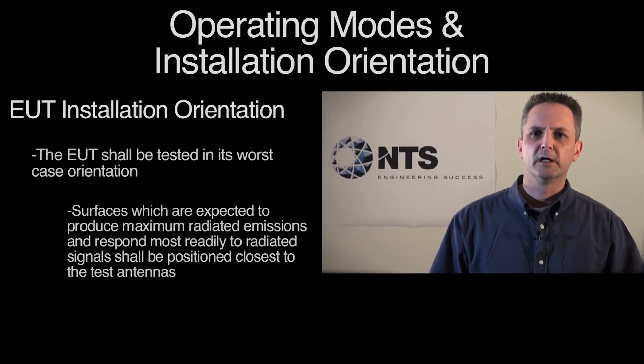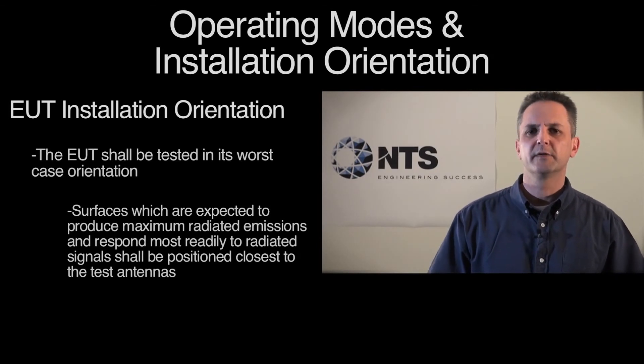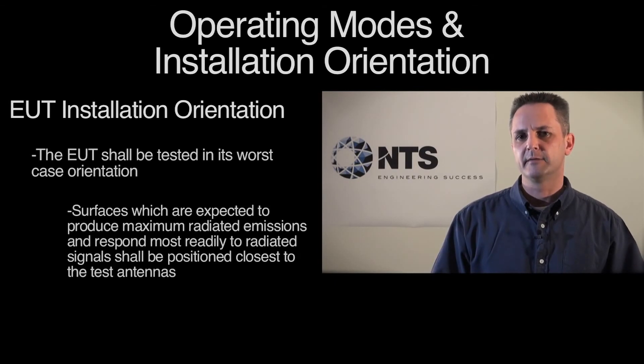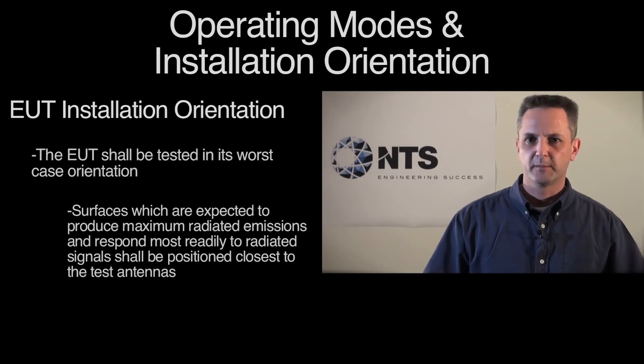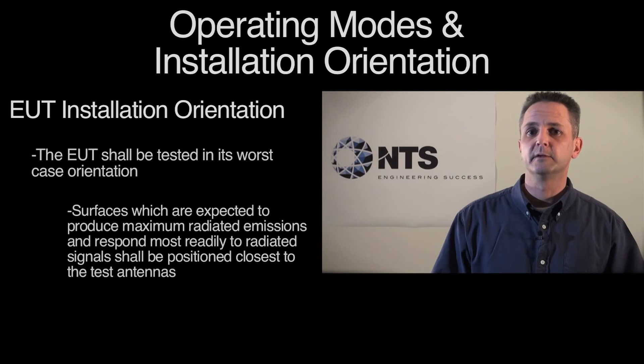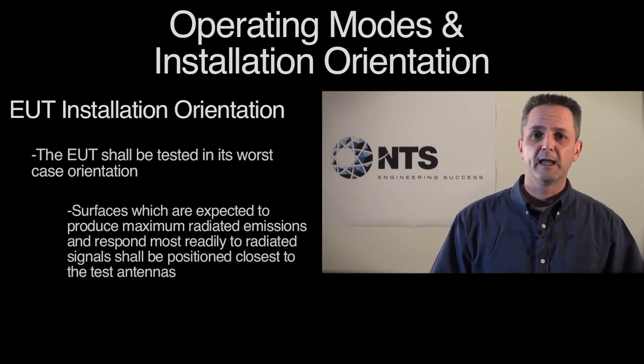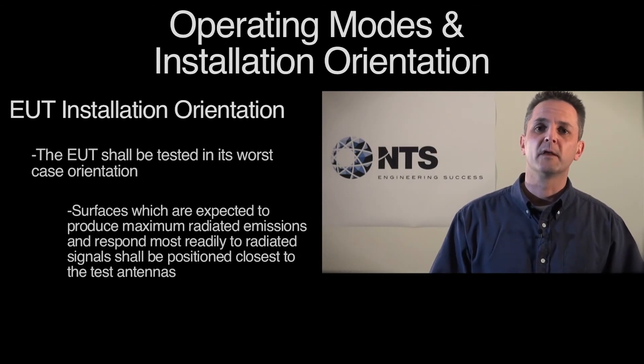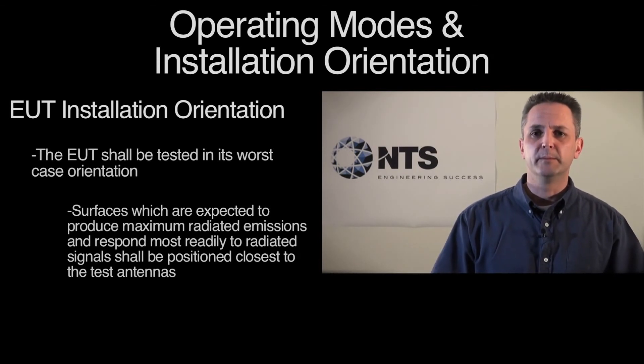In general terms, you look at the equipment to determine where it's most likely to have an emissions or susceptibility issue. Checking for large cable connectors, large interface plates, large LCD screens and displays, gasket areas, latches, doors, and covers are likely to be good candidates for that type of issue.